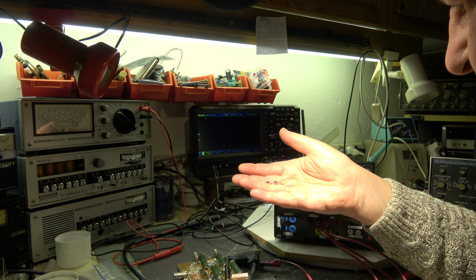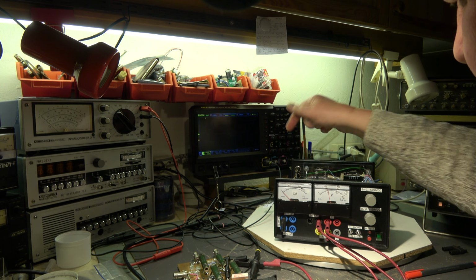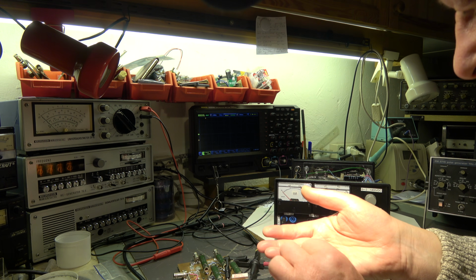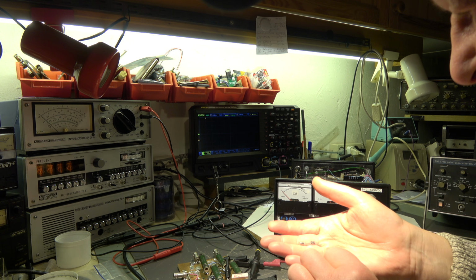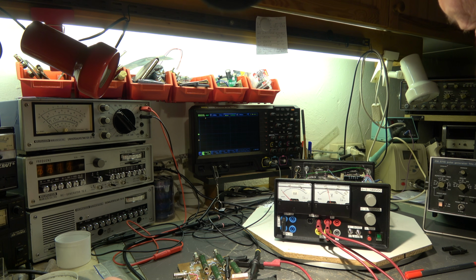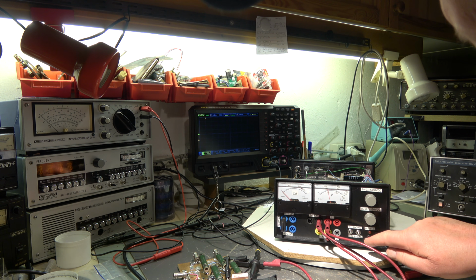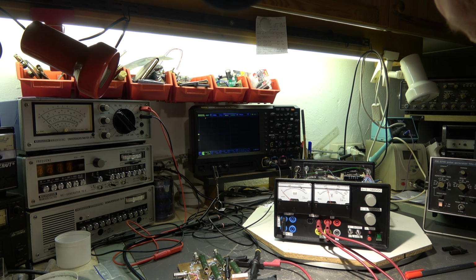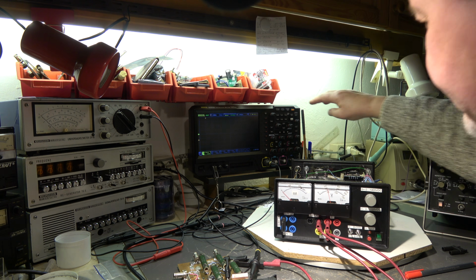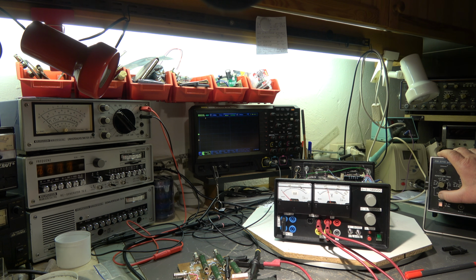The reason is the primary fuse was blown. It's a fuse on the line side. 800 milliamps, medium blow. I have a new fuse in it. Maybe the old fuse got a little bit too many short circuit tries, and therefore the fuse was damaged, pre-damaged, preloaded. So I have it again. We have 300 volt, 100 volt. Now a lower setting. Scope is set to single shot again. And now let's have a look at it.